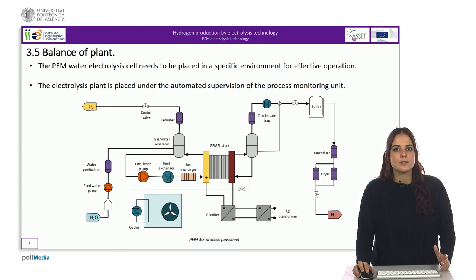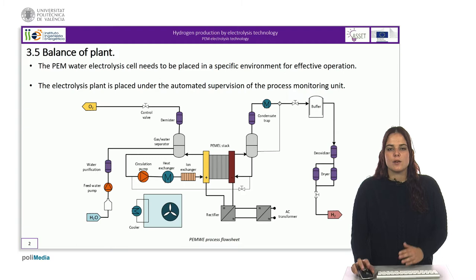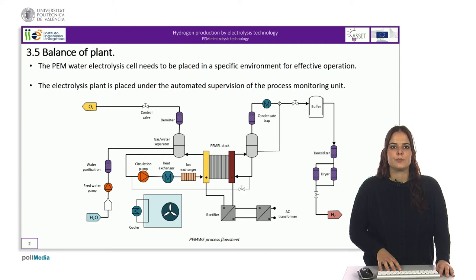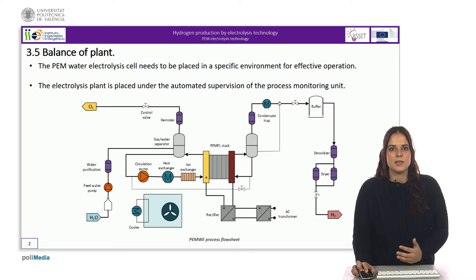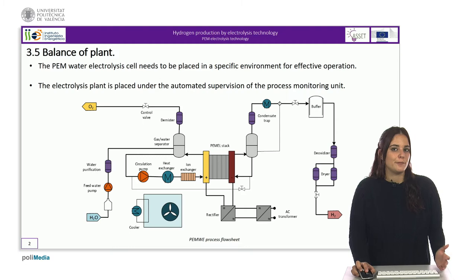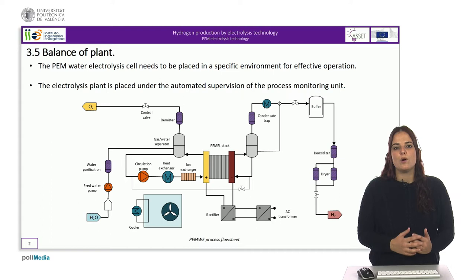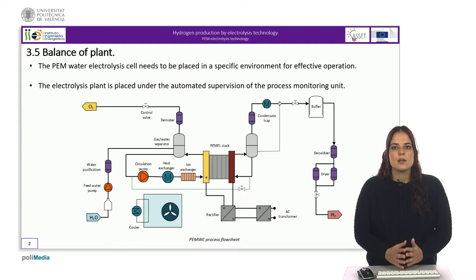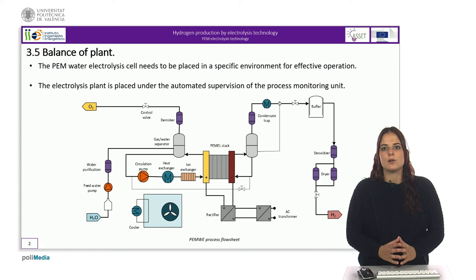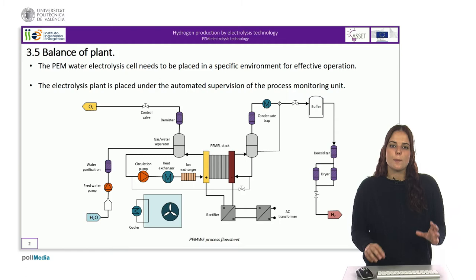The PEM water electrolysis cell or stack needs to be placed in a specific environment for effective operation. For example, it is necessary to provide water of adequate purity and to supply that water to the cell or stack in order to feed the reaction. It is also important to remove the excess heat produced by internal dissipation during operation at non-zero current density. It is required to maintain the level of water purity during operation and to recycle the flow of electroosmotic water, and to extract from the cell the reaction products and treat them to adjust their chemical composition to downstream requirements. All these operations are achieved by a number of dedicated subunits that form together the so-called balance of plant.